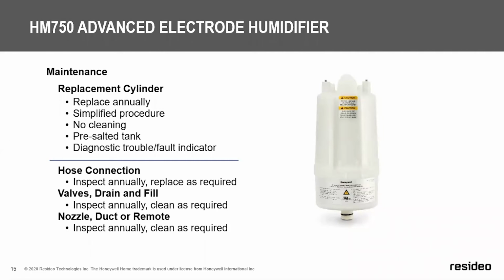The tank itself is pre-salted to give you a jump start on conductivity by providing minerals in the water. The hose connection should be inspected annually. If needed, if worn, it can be replaced. Again, the drain and fill valve should be inspected and cleaned so that the O-ring seats in there without any gouges. And if needed, the nozzle itself could be replaced if it starts to show wear or deterioration.